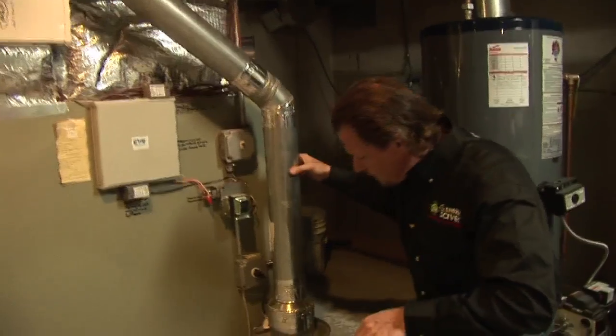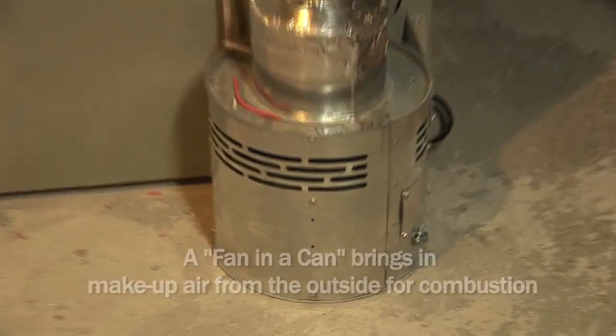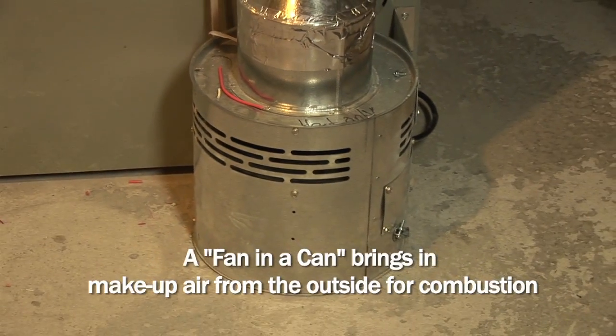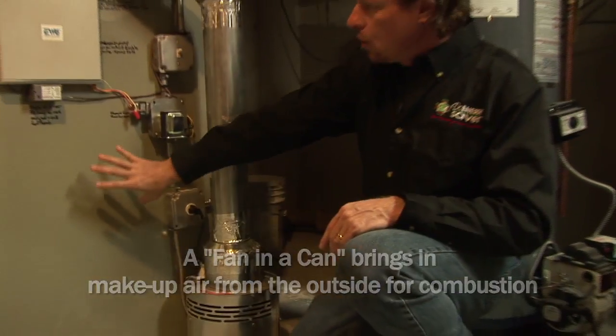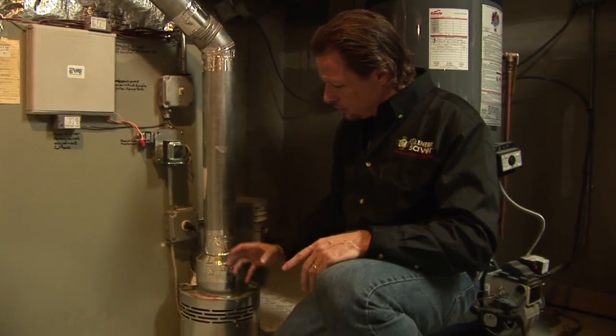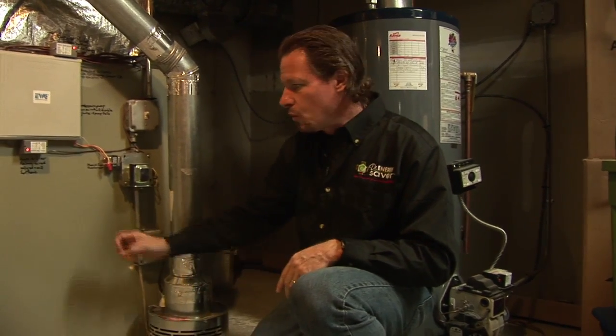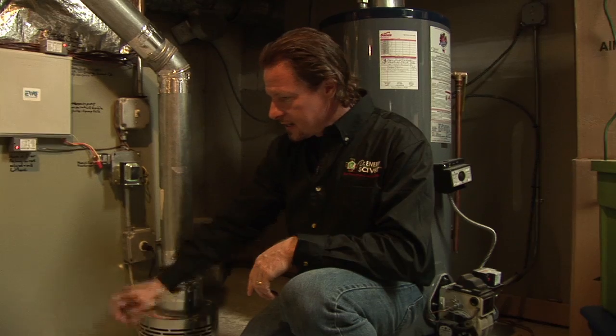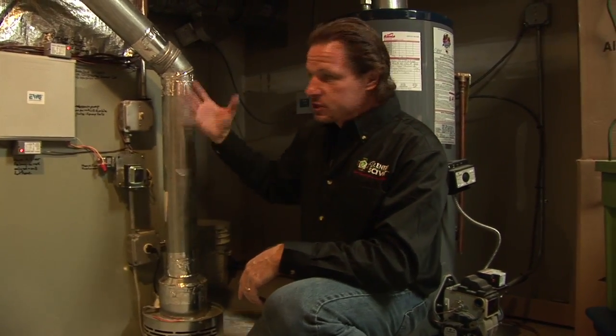Now, this particular piece of equipment has what we sometimes refer to as a fan in a can. Basically, it's makeup air, and there's a fan inside here and a duct that goes to the outside, and only when the burner is running does this fan run to bring in makeup air into the basement so that we know where the conditioned air makeup is coming from. It's coming from outside through this duct, which is not necessarily a good thing. We're basically sucking in outside air and blowing it into the basement, but at least we know that there's going to be enough air for combustion and for makeup air while the oil furnace is running, and it's not going to cause any combustion problems because the basement is too depressurized.